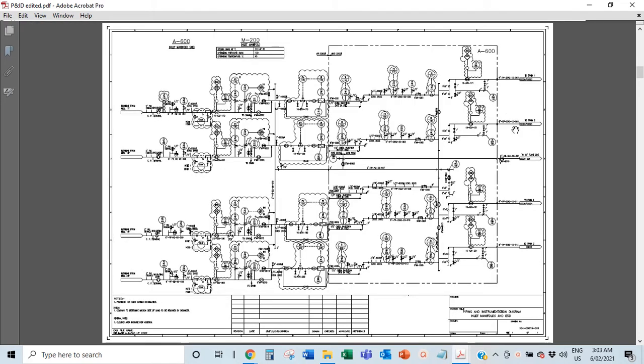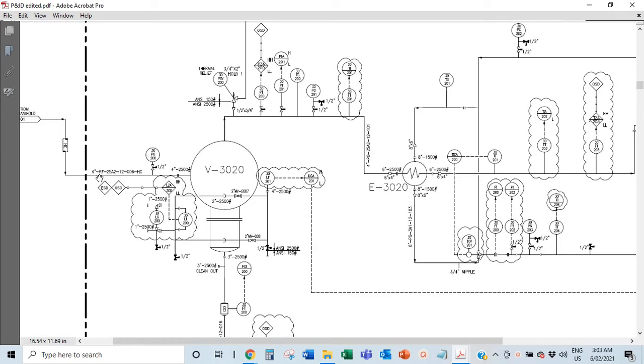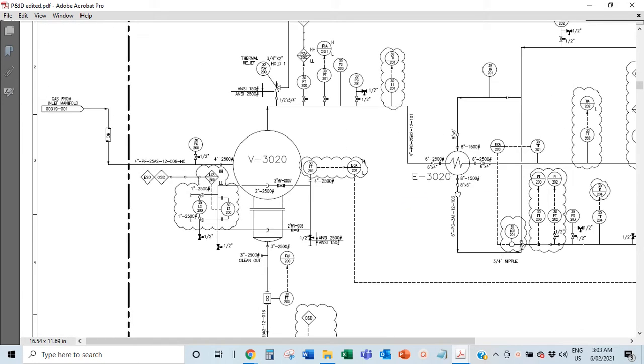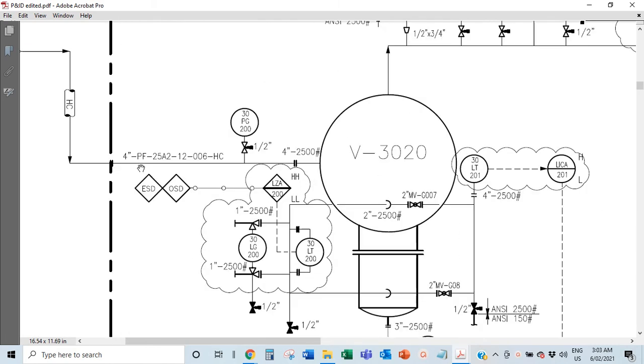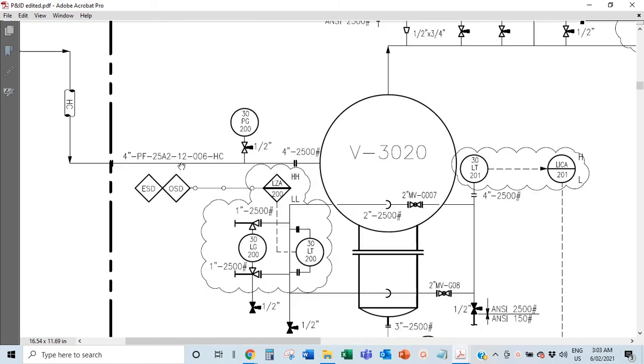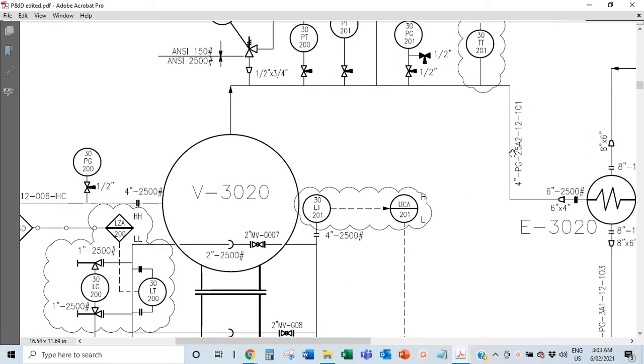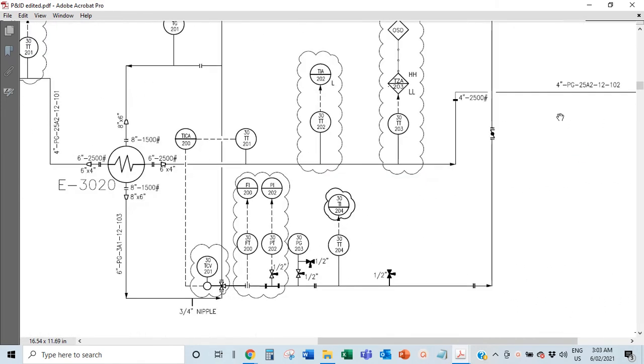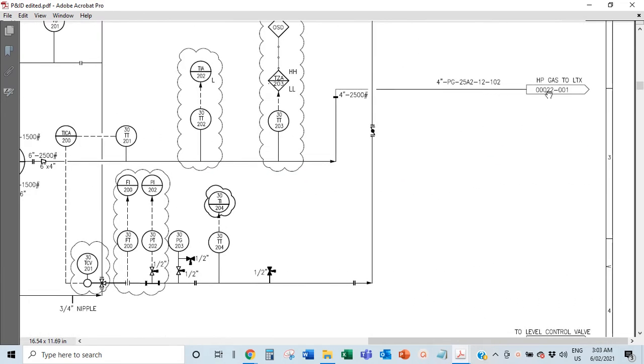You can see that these lines all go to page 20 — the second page. When you look at those flags here, they tell you the next place the line is going. If you're confused about a line, look at this line number — they are everywhere. You see them here and here. If you're not sure, just go to the page it references and look for that line number showing up there. That's how you keep piecing it together and everything starts to make sense.